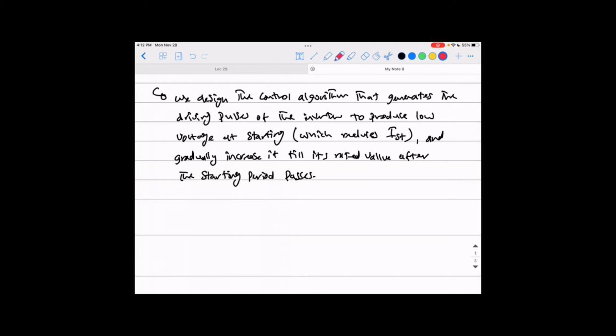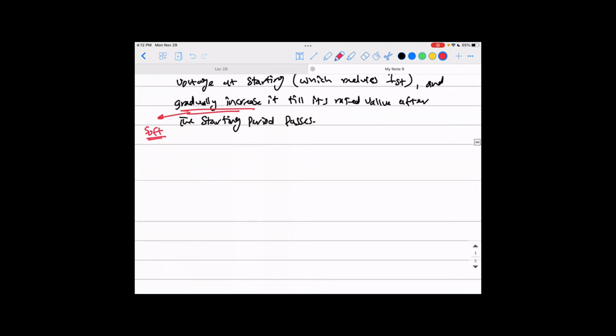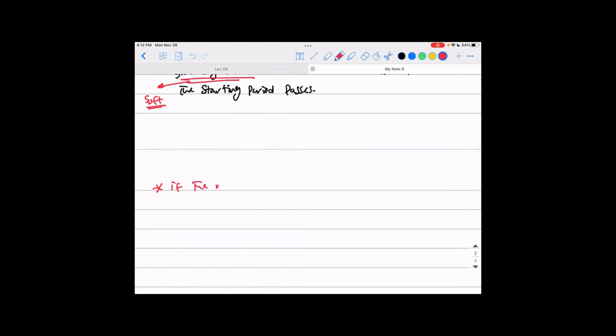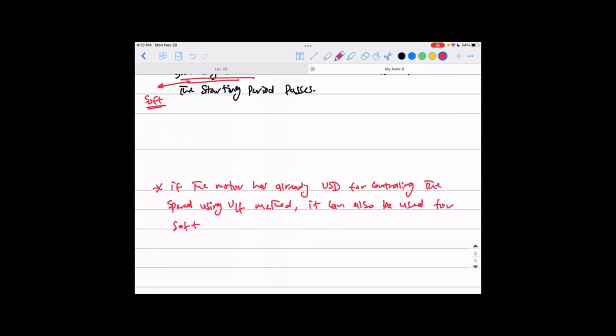Okay, and you have so much flexibility, gradually increasing the voltage, and that is why we call it a soft starter. Okay, guys, the whole point is, if the motor already has variable speed drives for controlling the speed using the V over F method, it can also be used for soft starting.